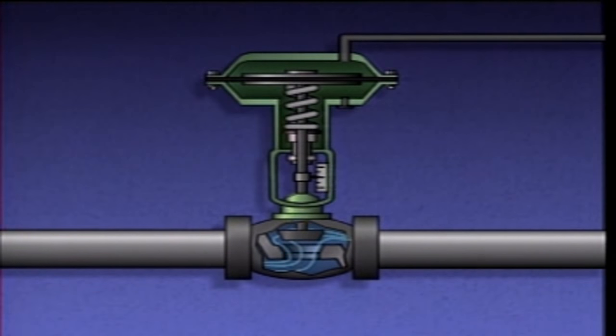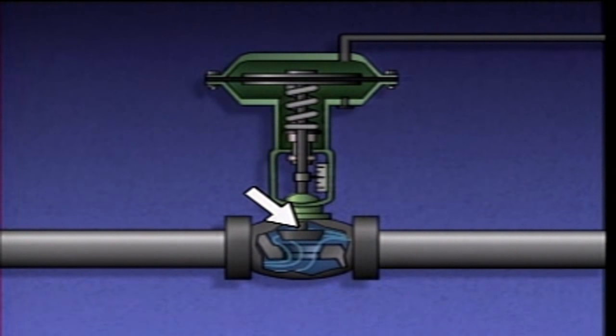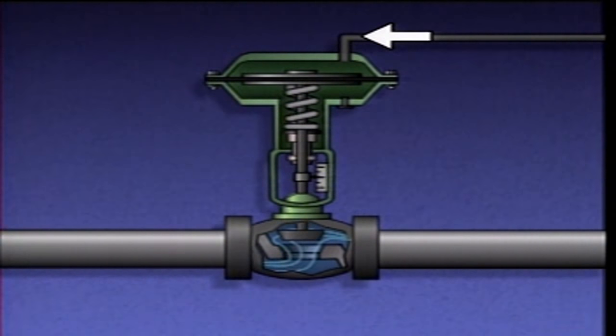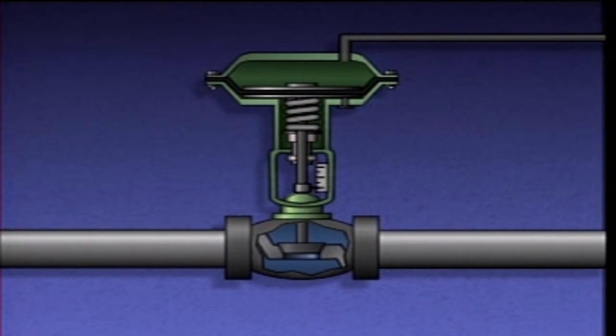The upper end of the actuator's stem is connected to the metal plates in the diaphragm, and the lower end moves the valve disc. When the actuator receives a signal from a controller to close the valve, air pressure is applied to the upper chamber, and the diaphragm and the actuator's stem are pushed downward.